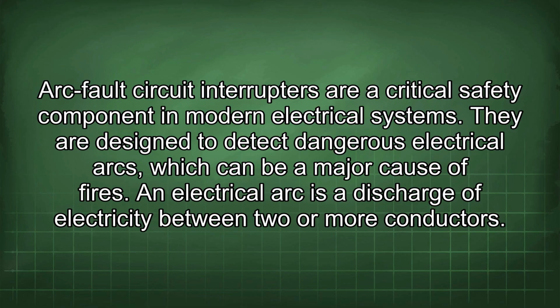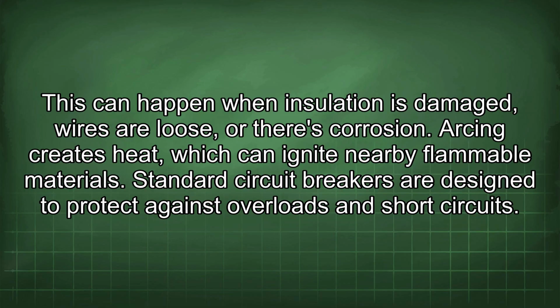Arc fault circuit interrupters are a critical safety component in modern electrical systems. They are designed to detect dangerous electrical arcs, which can be a major cause of fires. An electrical arc is a discharge of electricity between two or more conductors. This can happen when insulation is damaged, wires are loose, or there's corrosion. Arcing creates heat, which can ignite nearby flammable materials.